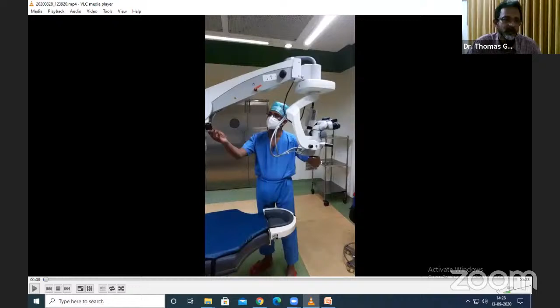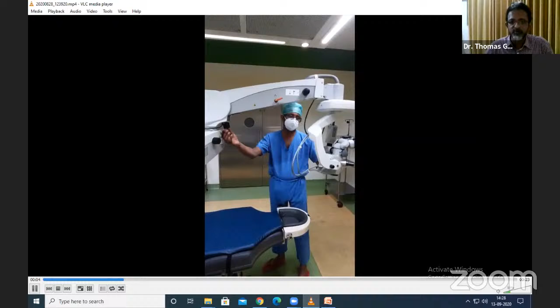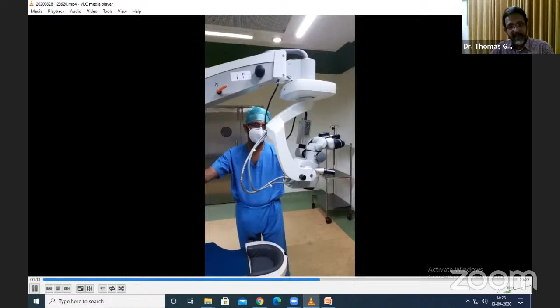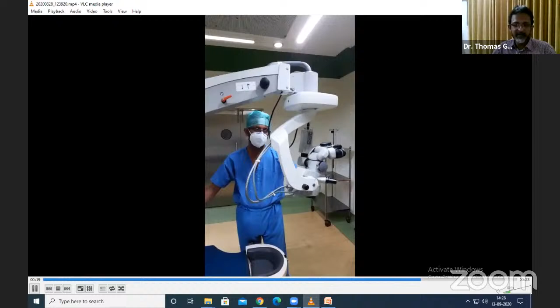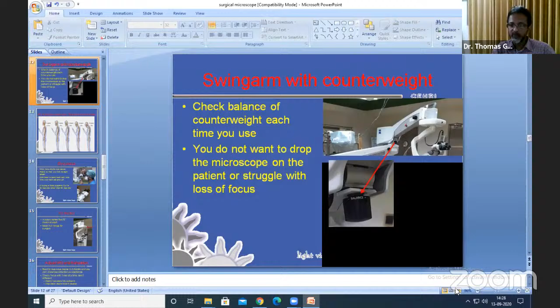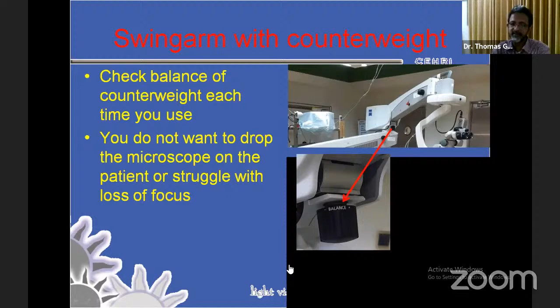So what you need to do is to gently push the microscope down or up. If it's accelerating, it is not balanced. You turn the knob either way and find out where it is balancing. The plus side adds to the counterweight, the minus side decreases the counterweight leverage, but it doesn't matter which side. You turn one way, if it's getting worse, you turn the other way. That's all. And finally, the microscope should not be freely moving off, and when you push it in one direction, it should stop after a small movement. It should not be accelerating in that direction, up or down.